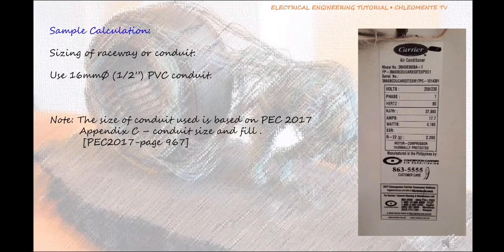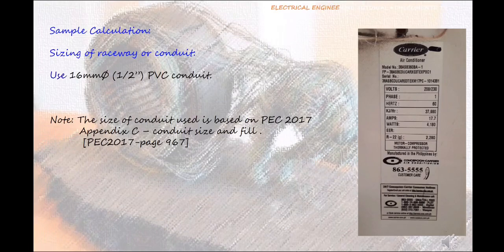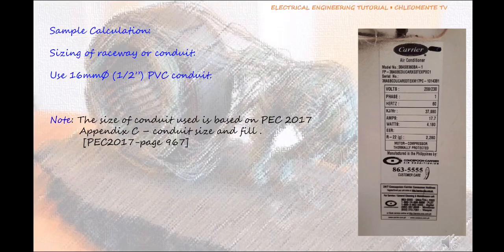Sizing of Raceway or Conduit. Use 16 millimeters diameter, half an inch, PVC conduit. Note: The size of conduit used is based on PEC 2017 Appendix C, Conduit Size and Fill, PEC 2017 Page 967.